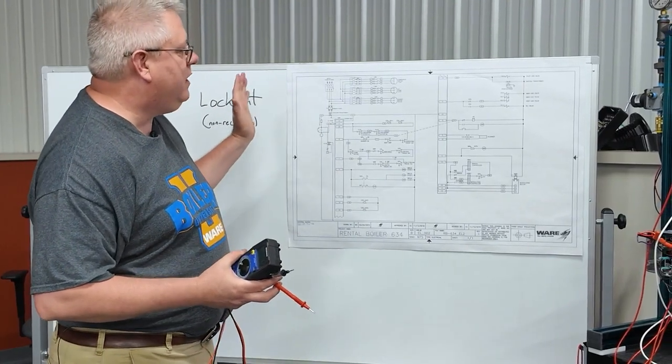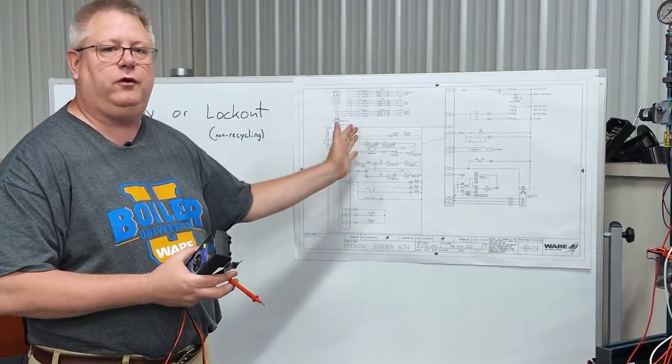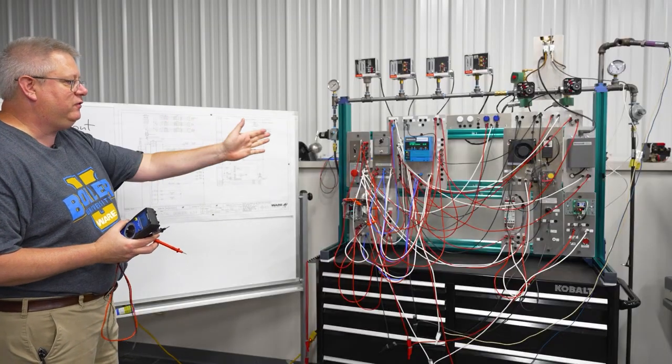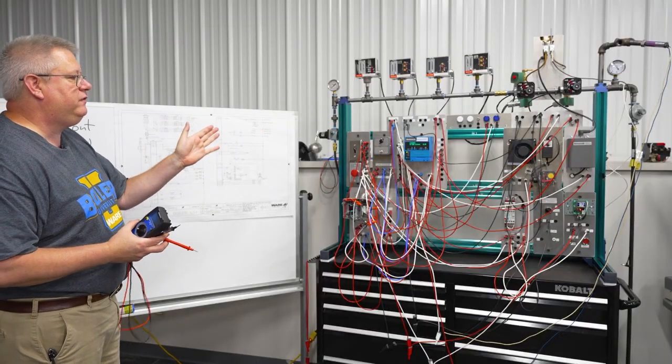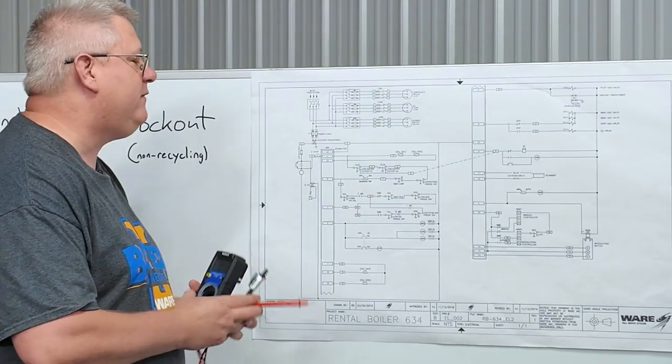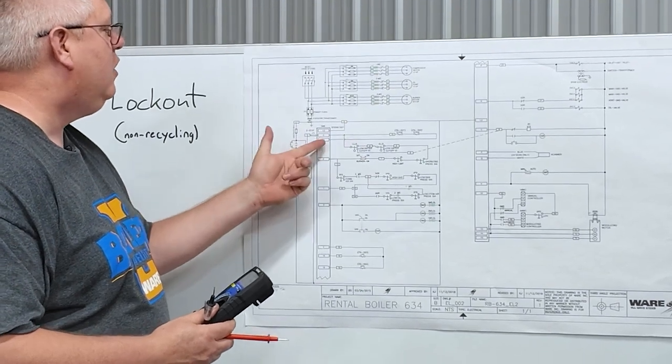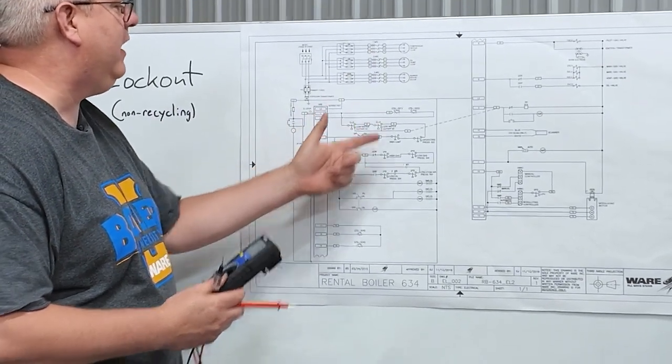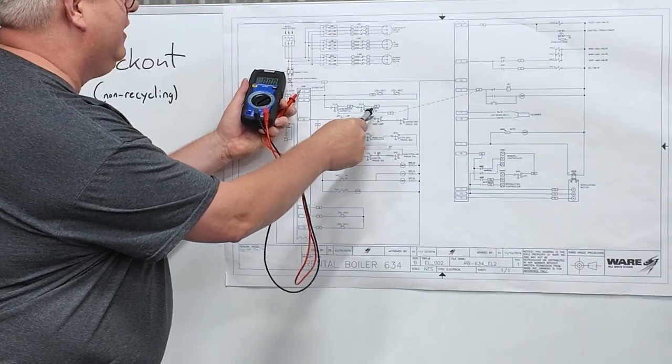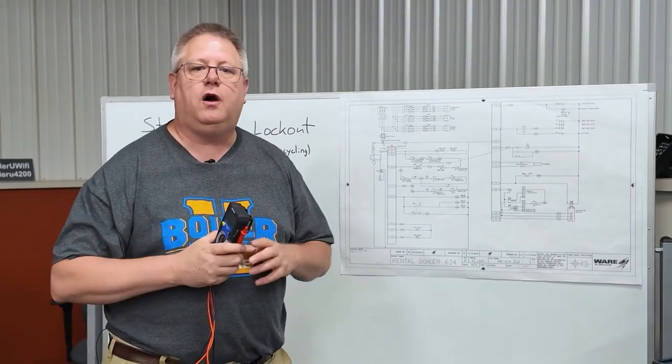The importance of a diagram is it really accelerates troubleshooting. On a unit without a print, I've got to chase wire through conduit to find which in a series of switches is tripped. But if I've got a print, I can simply look at the limit series and take a meter and test terminals in the panel and quickly narrow down where that problem is.